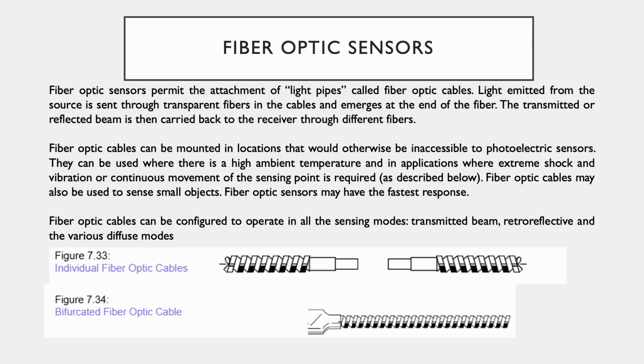Fiber optic cables may also be used to sense small objects. Fiber optics may have the fastest response. Fiber optic cables can be configured to operate in all sensing modes: transmitted beam, retroreflective, and the various diffuse modes. So if you look at it, fiber optic cable, even if your environment is uncertain or hot or cold, because it doesn't rely on the outside environment like others that rely on sound waves, here you have a cable, it's direct.